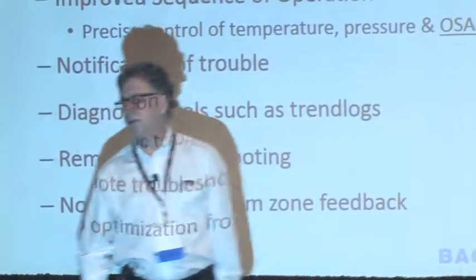So if we're looking at a system here with an air handler alone, let's say you come in and you want to do just the air handlers. Well, what are you going to see? You're going to see a very much improved sequence of operation. It's actually going to have a much more complicated system there. You're going to have things like optimum start along with the scheduling, maybe even optimum stop. Very precise control of the temperature, but probably the most important part of this one is you end up having much better and much more accurate control of the outside air CFM that's coming into that unit.